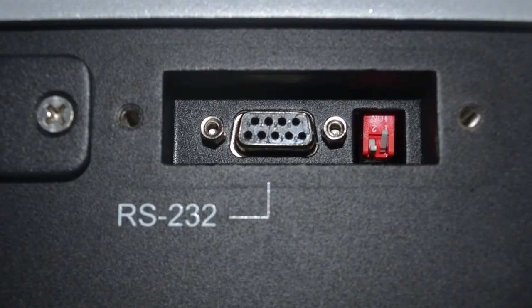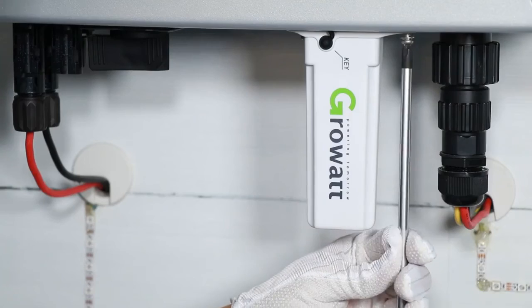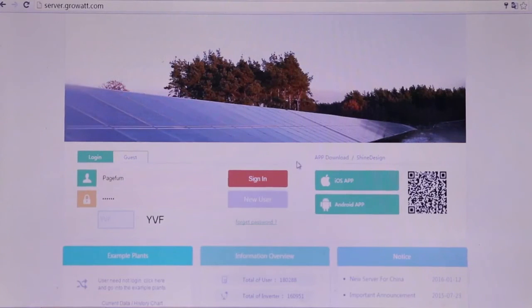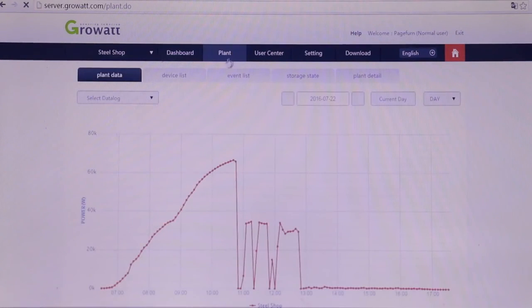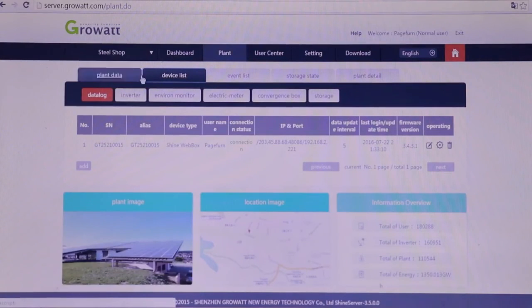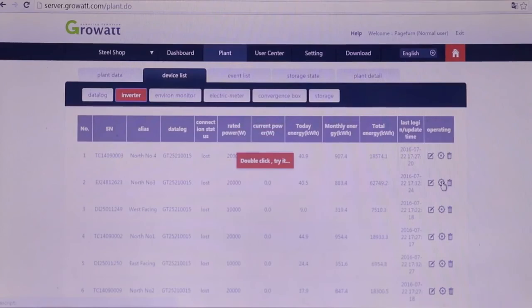When RS-232 is connecting with an external monitoring device, DIP switch 1 must be set to ON in order to power on the external device — for example, an external Wi-Fi module or RF module. We suggest monitoring the inverter via the Growatt Wi-Fi module. It allows customers to check production data on a mobile phone, tablet, or laptop wherever there is internet access. Moreover, the monitoring system can also upgrade inverter firmware and adjust parameters remotely.